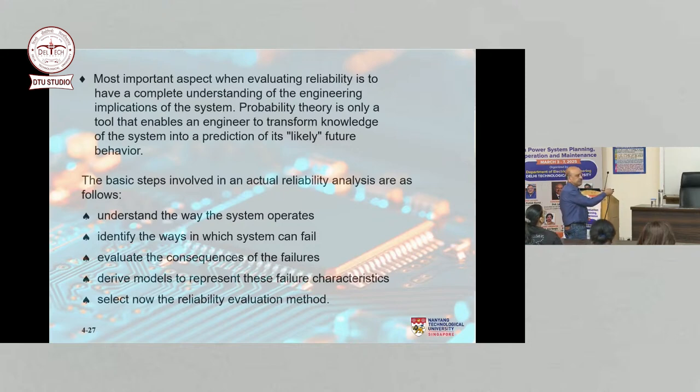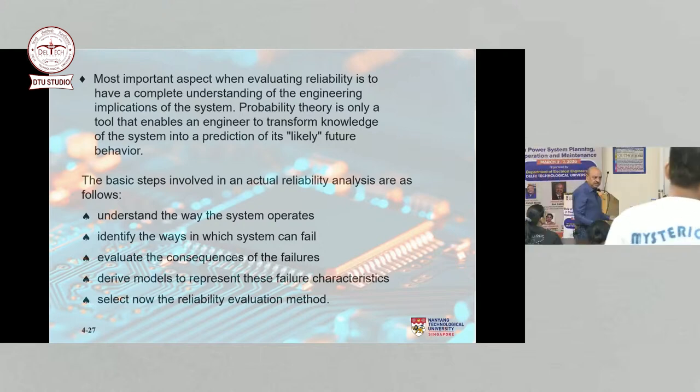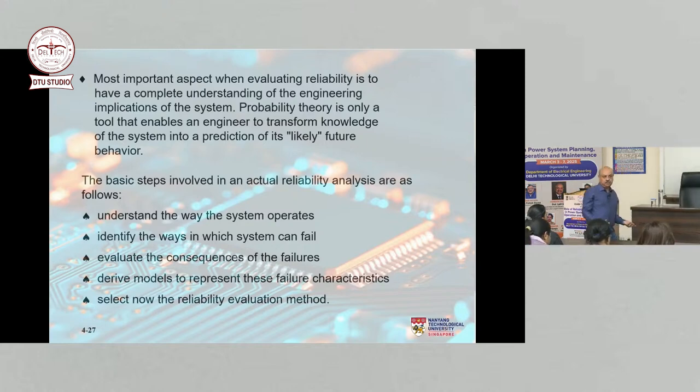Understand the way in which the system operates. Identify the ways in which it can fail. And then evaluate the consequences of failures. Are those failures acceptable? If they're acceptable, then we don't need to worry too much about them. But if they're not, then we should know what the consequences are and how to deal with them. And then derive models to represent these failures. What kind of model are you going to use? Approximate model, detailed model? Things like that. And last but not least, now you select the reliability evaluation method.